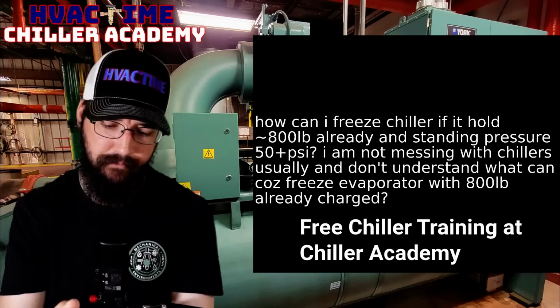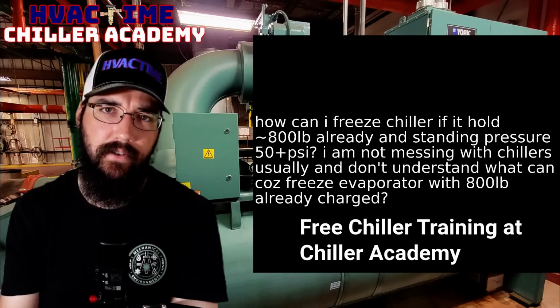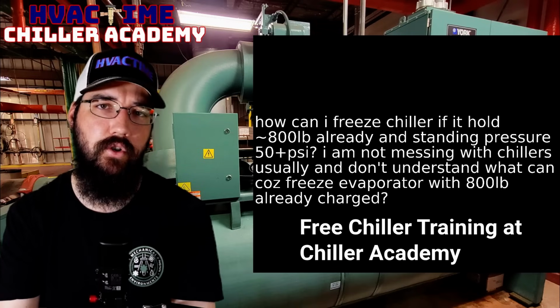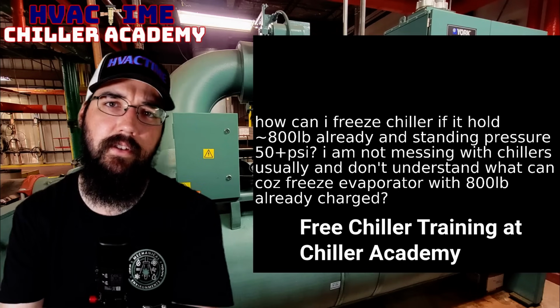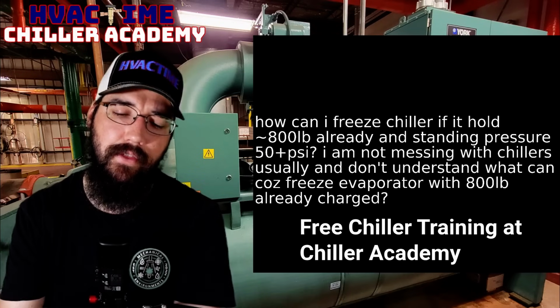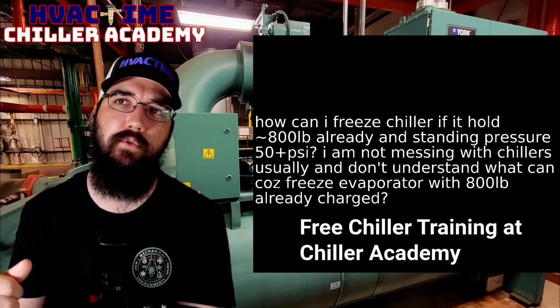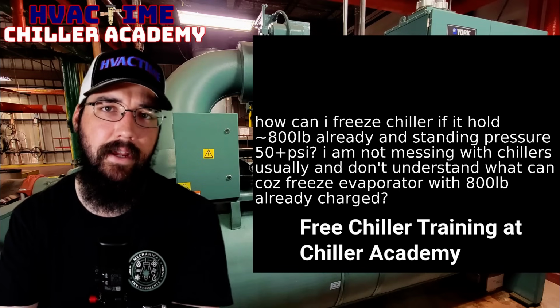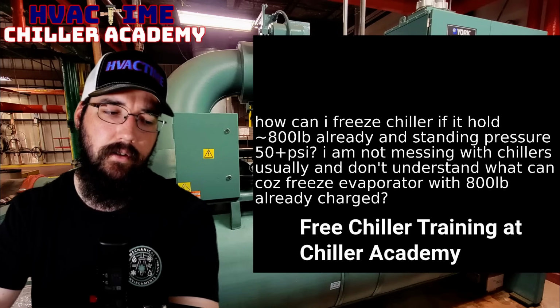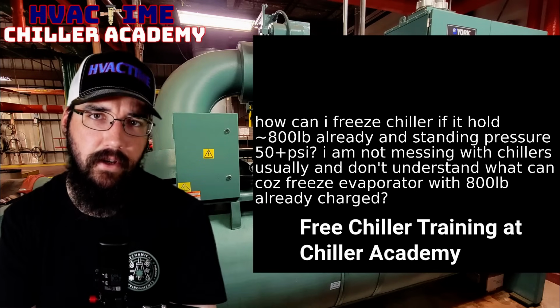That is the main concept that we're having to think about and work around: what is the freezing saturation pressure, and let's get above that. And this is where you can charge vapor. I've talked about this a lot recently, where if you pre-charge vapor into the chiller and get that pressure up, then charging liquid from there is far less of a risk versus if you tried to send straight liquid in right out the gate after your evacuation, and then you end up causing the liquid refrigerant to make contact with the water.